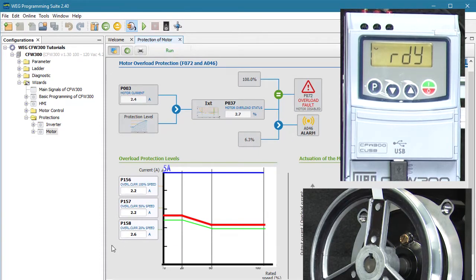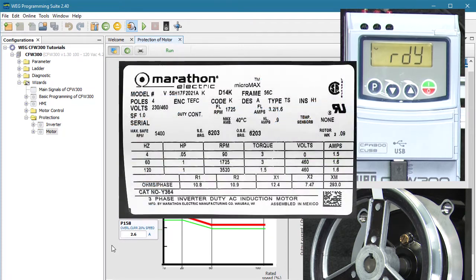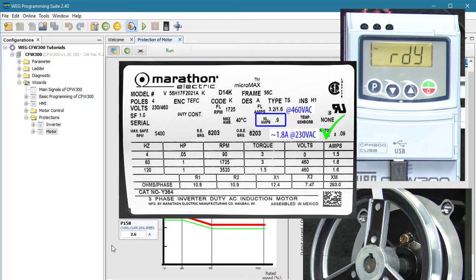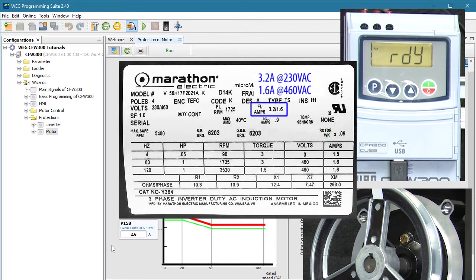Let's do a quick check. The motor nameplate says we should be drawing about 0.9 amps at 460 volts under no load. So we would roughly double that for 230 volts, and sure enough it's pretty close to 2 amps. Everything makes sense.